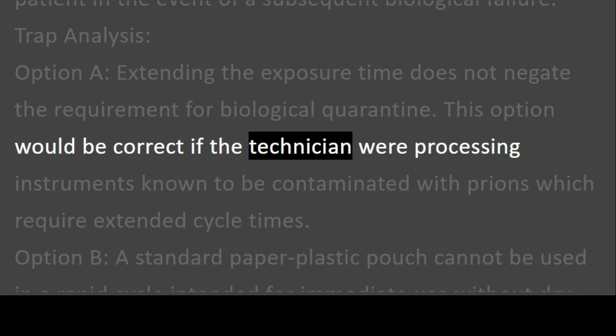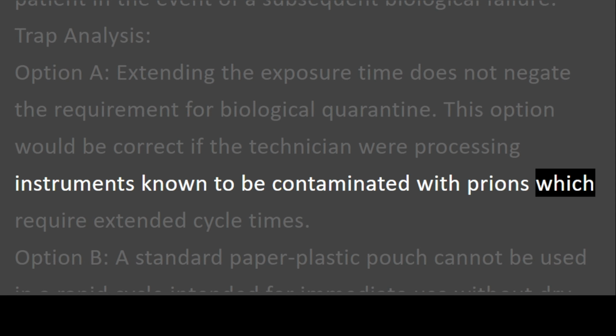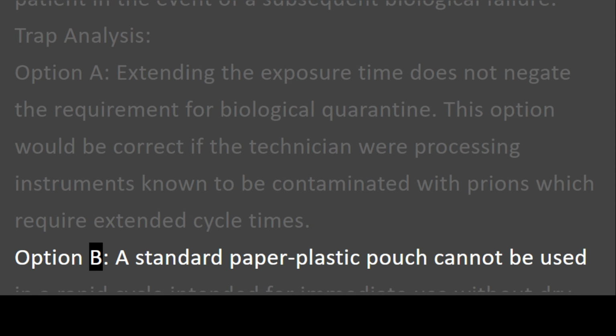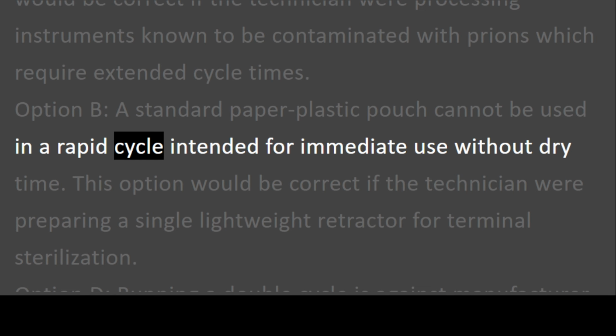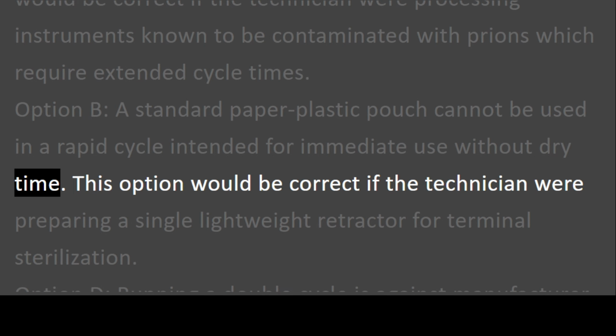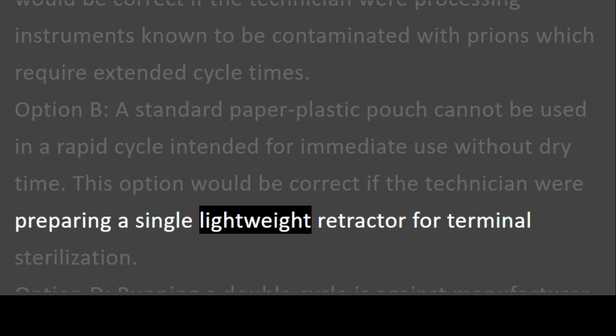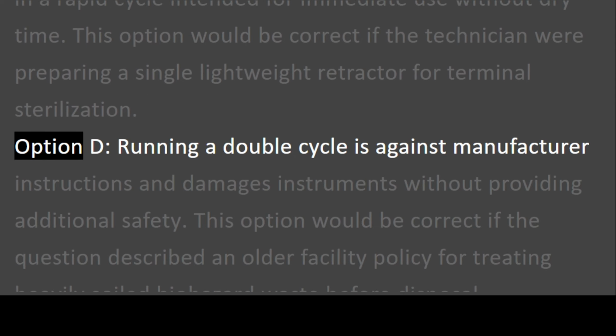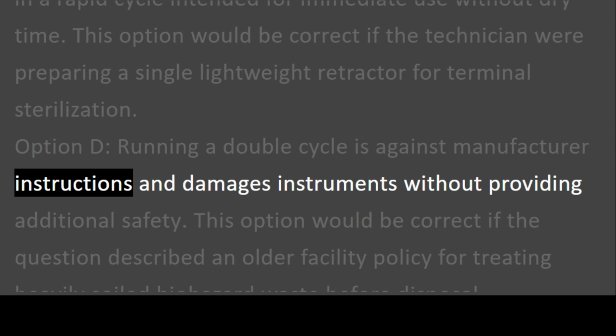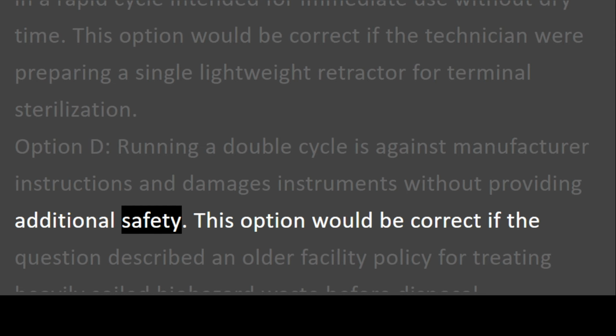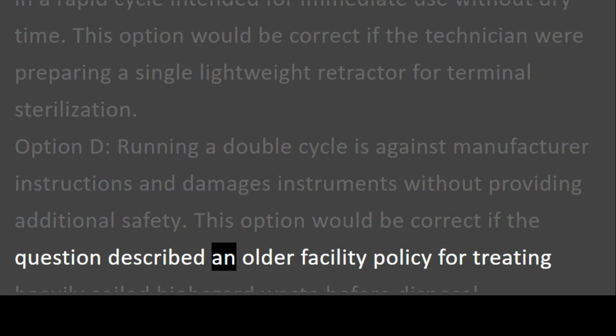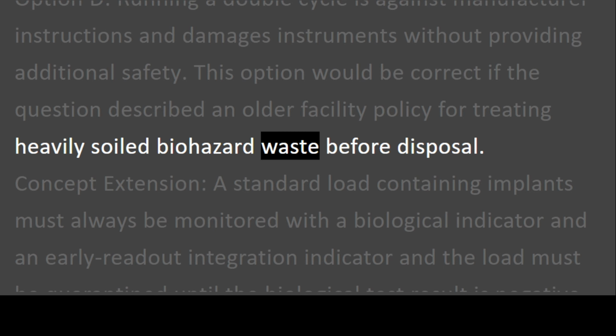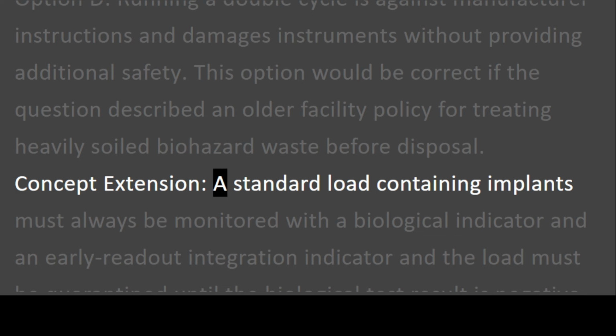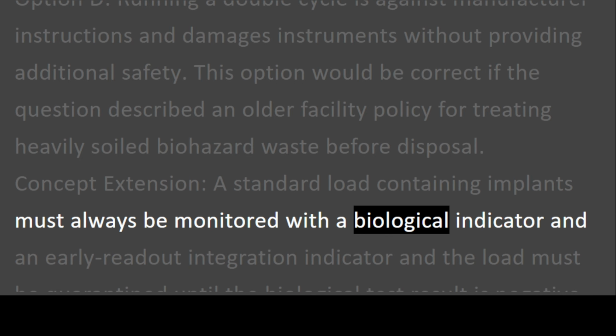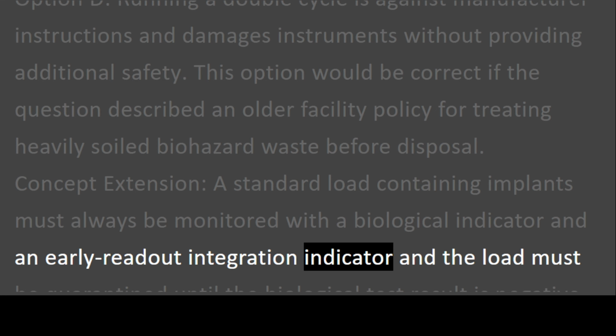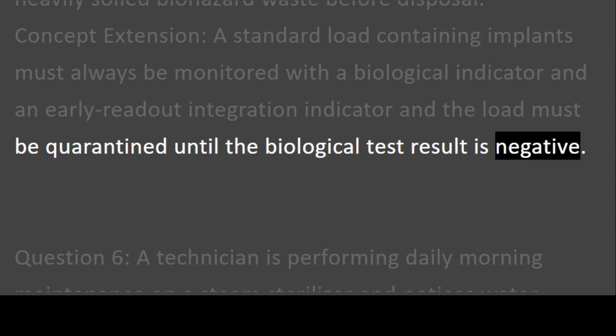This option would be correct if the technician were processing instruments known to be contaminated with prion, which require extended cycle times. Option B. A standard paper plastic pouch cannot be used in a rapid cycle intended for immediate use without dry time. This option would be correct if the technician were preparing a single lightweight retractor for terminal sterilization. Option D. Running a double cycle is against manufacturer instructions and damages instruments without providing additional safety. This option would be correct if the question described an older facility policy for treating heavily soiled biohazard waste before disposal. Concept extension. A standard load containing implants must always be monitored with a biological indicator and an early readout integration indicator, and the load must be quarantined until the biological test result is negative.